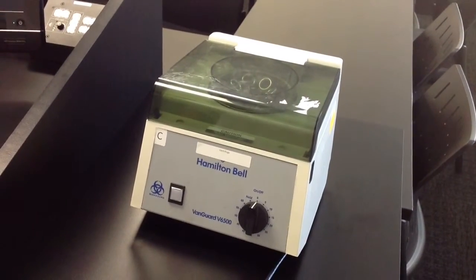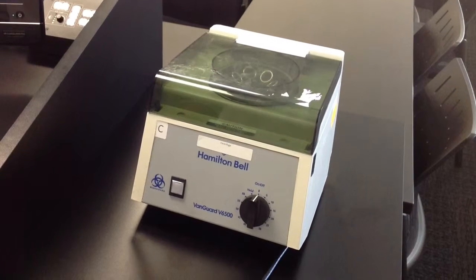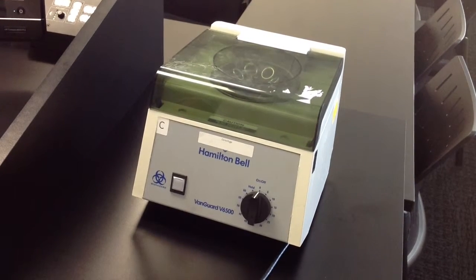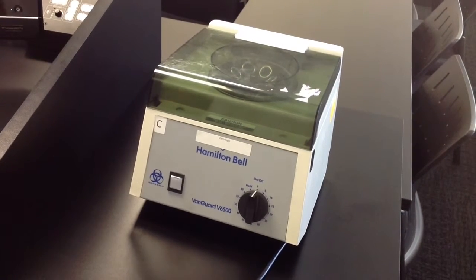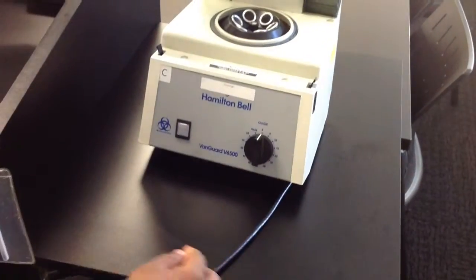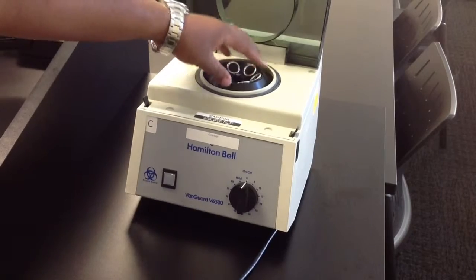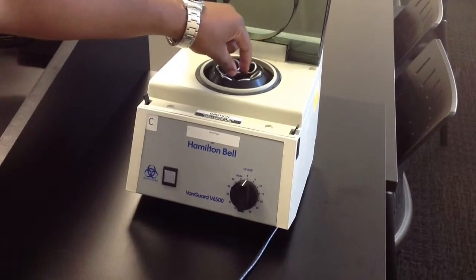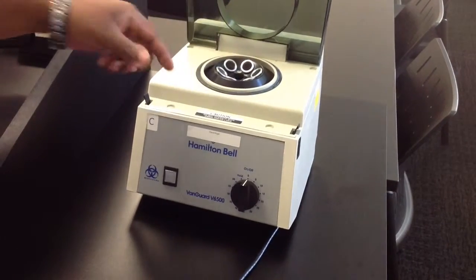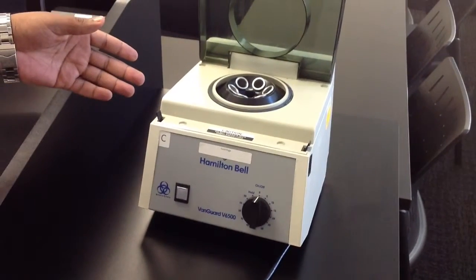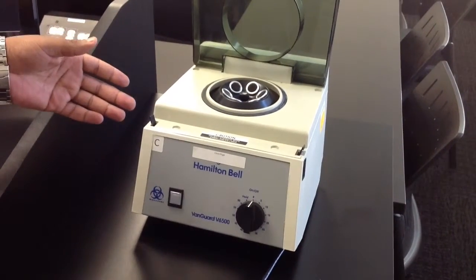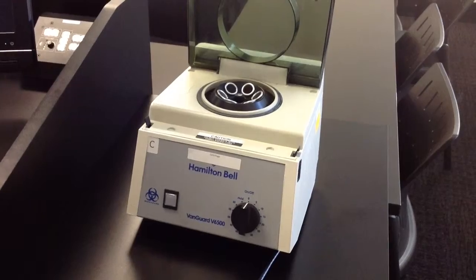Okay, a centrifuge. A centrifuge is a mechanical device that can subject experimental samples to a sustained centrifugal force. The first part of the centrifuge that we find, even though you can't see it here, will be the drive mechanism. It's actually located beneath this area here. This would be the drive shaft, and they're either electric motors, oil turbine motors, or air pump motors. In this smaller model, we have an electrical motor.